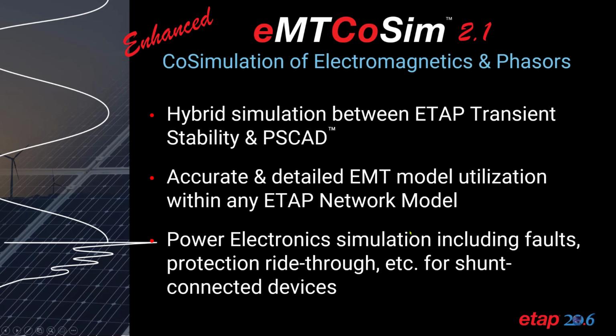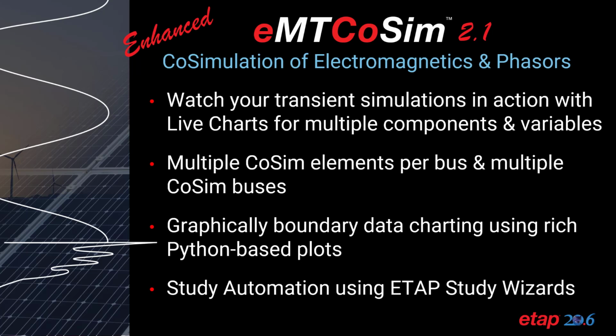ETAP EMT CoSim is now on version 2.1. It allows for co-simulation of electromagnetics and phasors. This hybrid simulation exists between ETAP transient stability and PSCAD application, as well as ETAP EMT. Accurate and detailed EMT model utilization can be done within any ETAP network model. And the power electronics simulation includes faults, protection ride-through, and many more for any shunt-connected device.